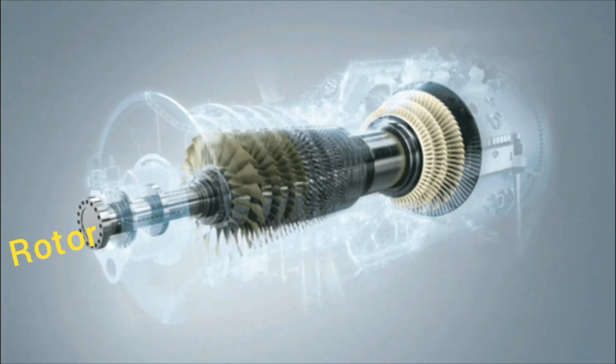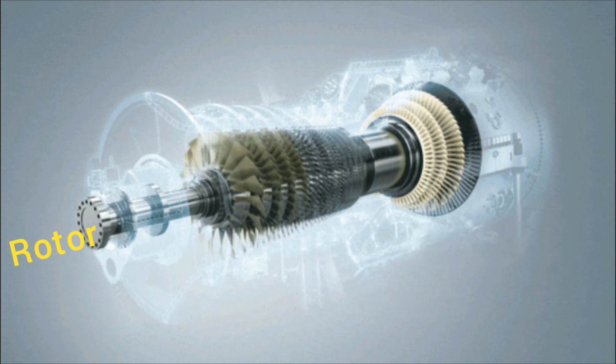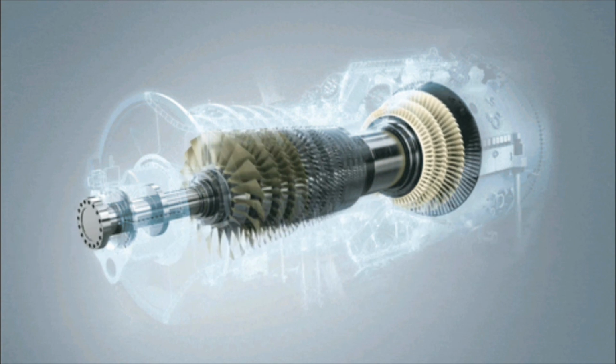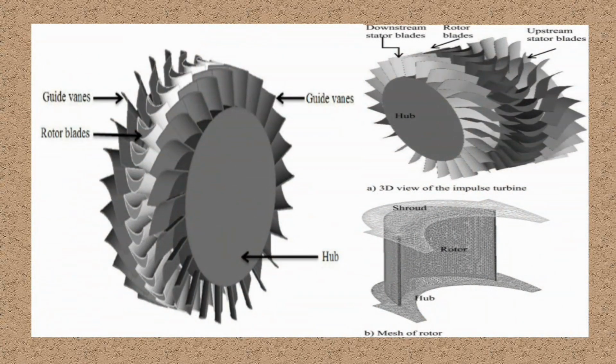The steam turbine rotors must be designed with the most care as it is mostly the highly stressed component in the turbine. The design of the turbine rotor depends on the operating principle of the turbine. In the impulse turbine, the pressure drops across the stationary blades. The stationary blades are mounted in the diaphragm and the moving blades are fixed or forged on the rotor. Steam leakage is in between the stationary blades and the rotor. The leakage rate is controlled by labyrinth seals. This construction requires a disc rotor. The rotor blades are symmetrical in shape in case of impulse turbine.